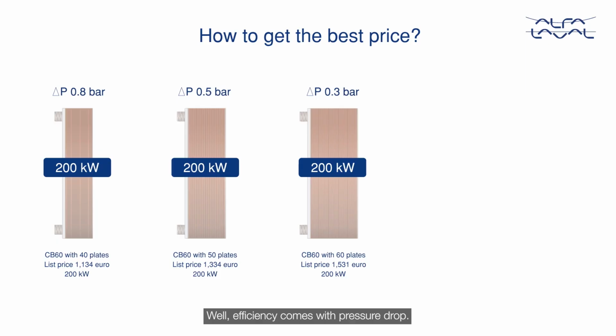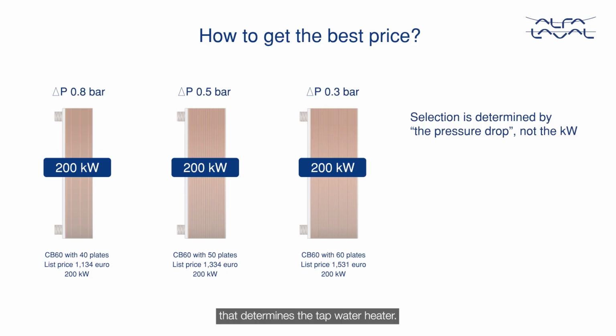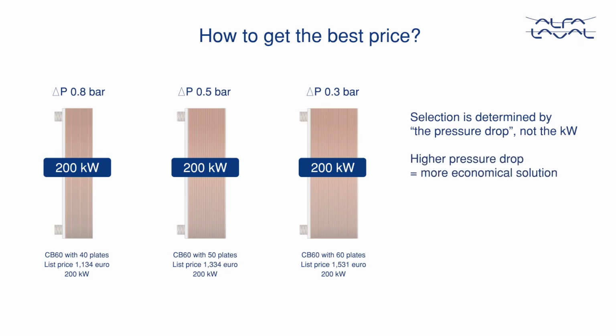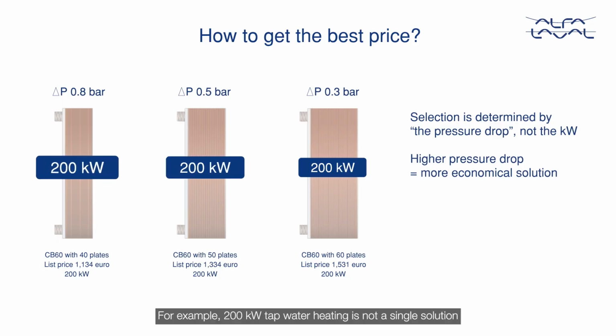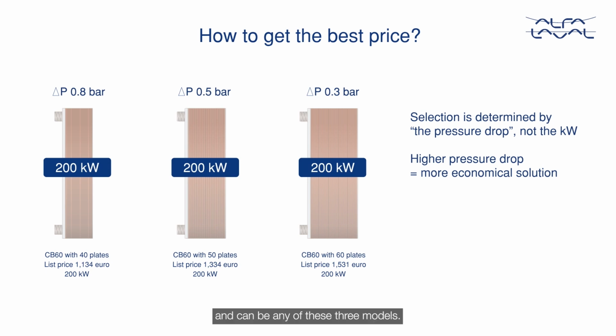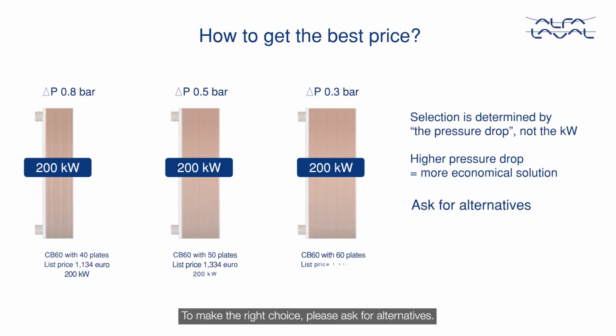How to get the best price? Well, efficiency comes with pressure drop. Remember, it is not the kilowatt capacity or the flow rate that determines the tap water heater. It is the pressure drop across the unit. For example, 200 kilowatt tap water heating is not a single solution and can be any of these 3 models. Each of these will deliver 200 kilowatts of performance, but with a different pressure drop on the boiler side. To make the right choice, please ask for alternatives.